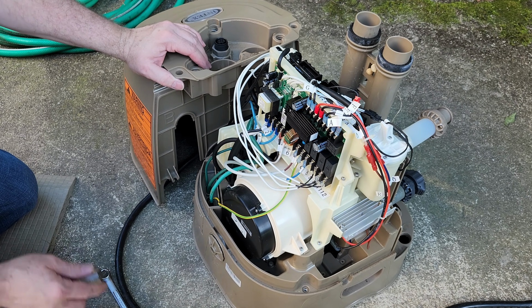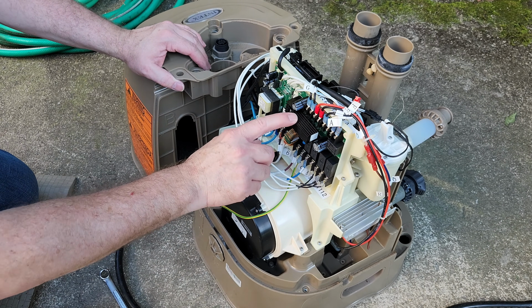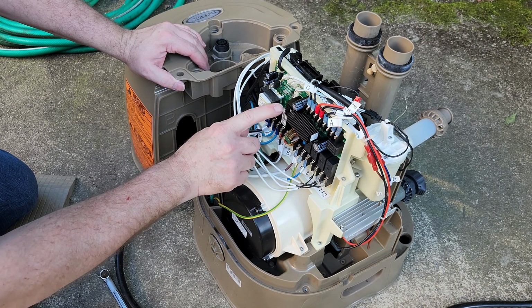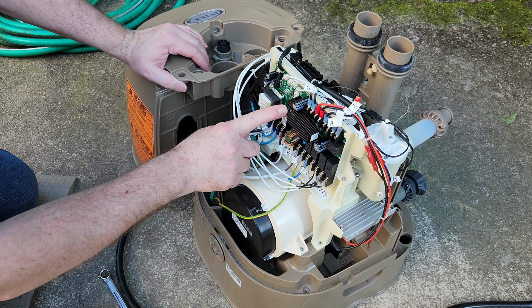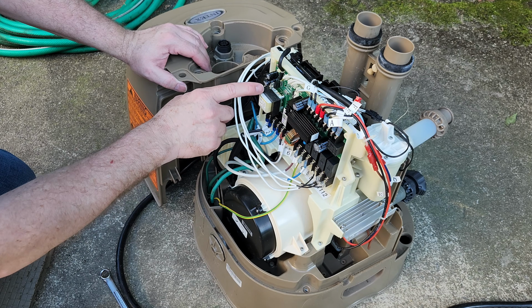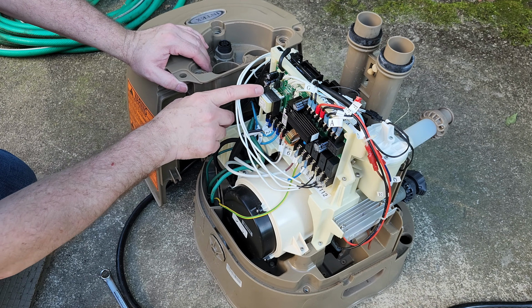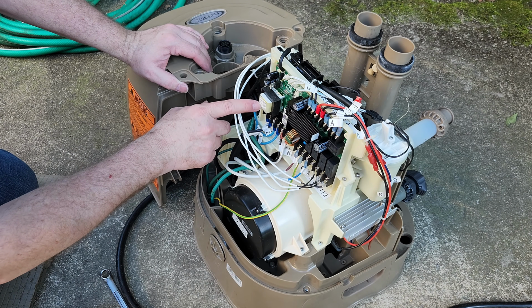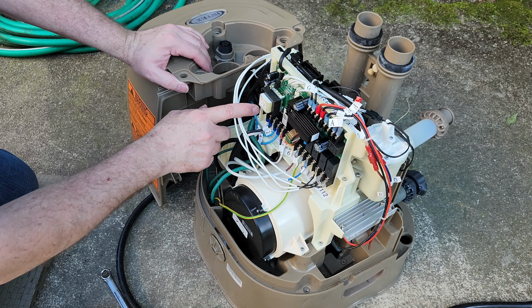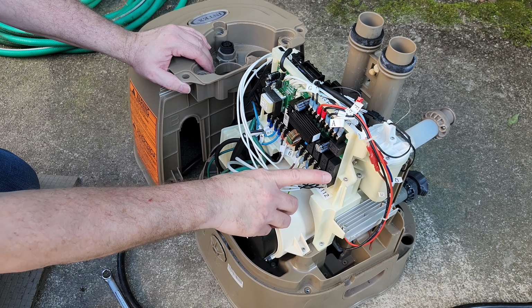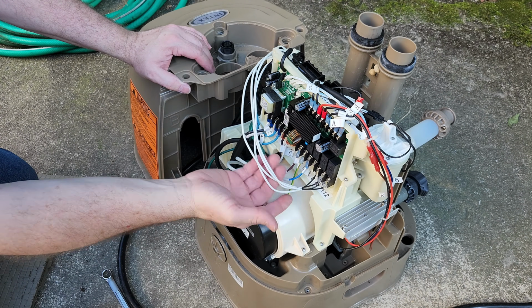I'm going to go through with a screwdriver and make sure all the connections are tight, and all the capacitors look good—no bulged caps, nothing obvious, no corrosion, no hot spots around the transformer or the cap over here on this part of the power supply. It looks good. We see these relays here for what I assume is multiple staging of the heat.